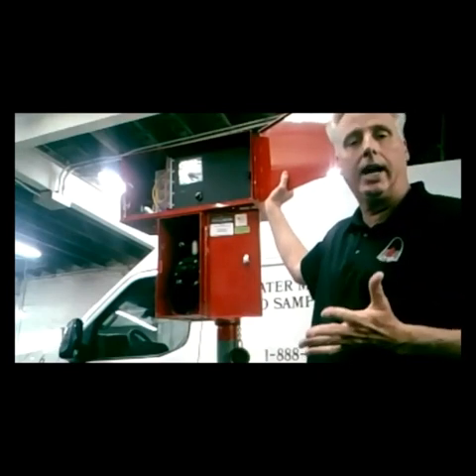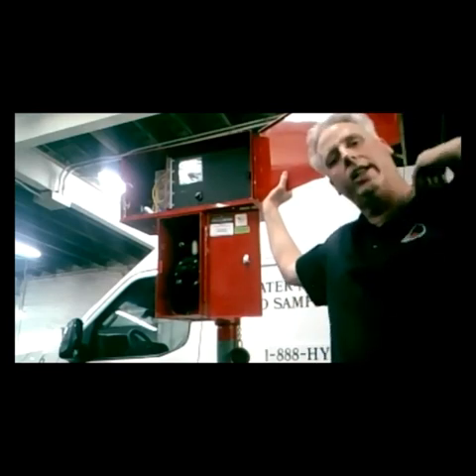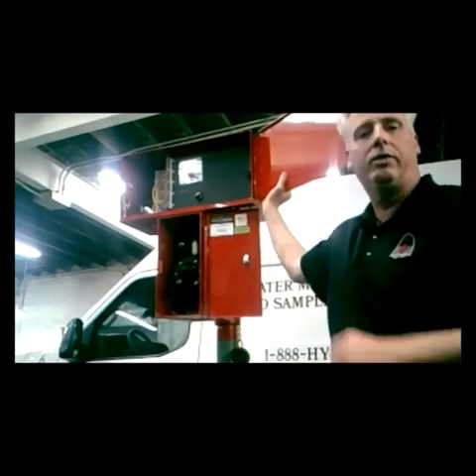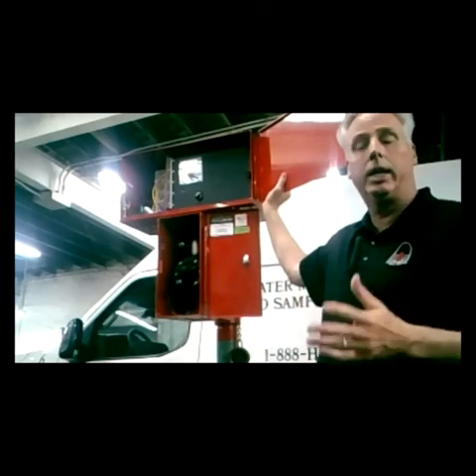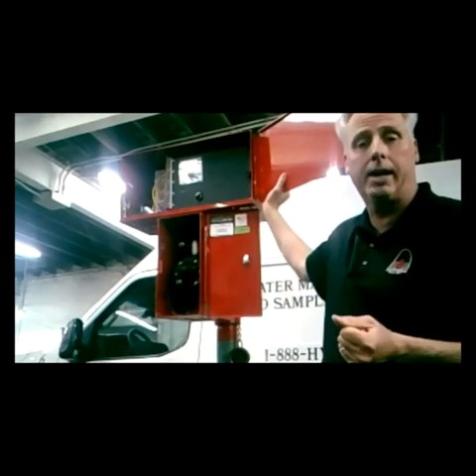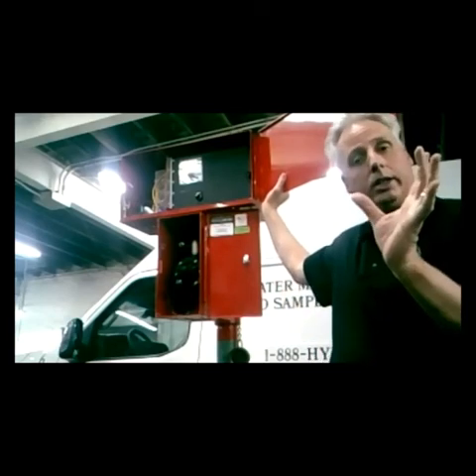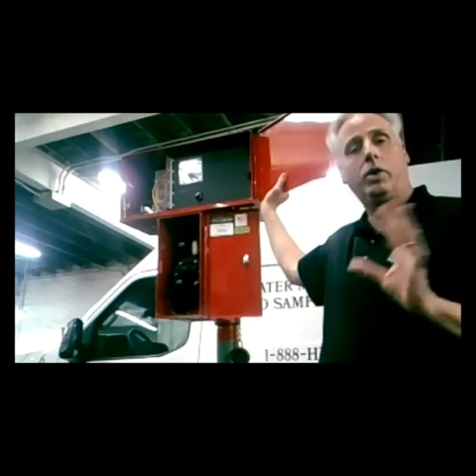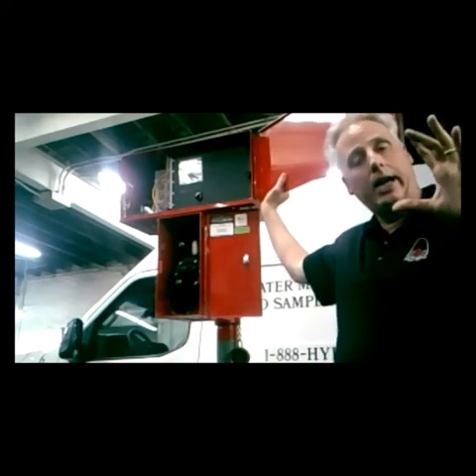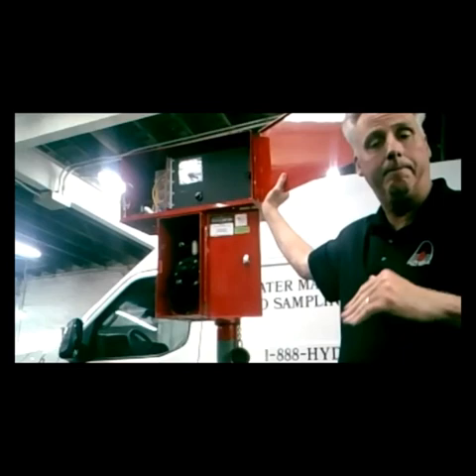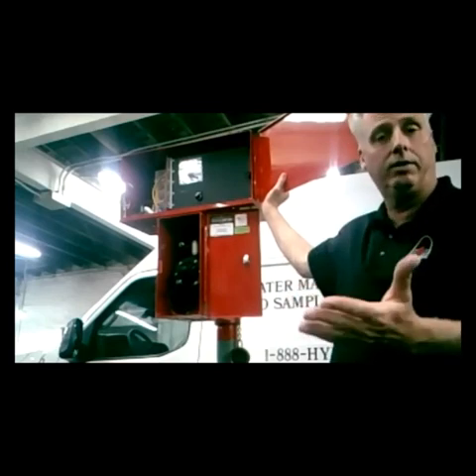A question I get a lot is, what if I don't want to flush during the day? How do I keep this device from flushing and taking samples during the day? The answer is you program the sample taking during certain hours. So if you don't want it to flush during the day, I take all my samples between midnight and 6 a.m., and if it takes a sample and needs to flush, it'll flush the line.